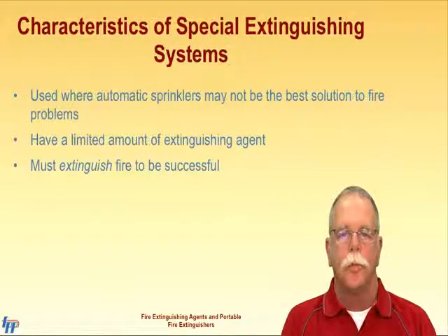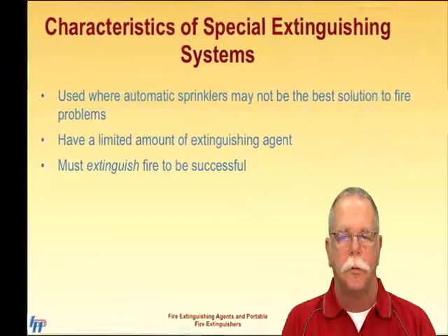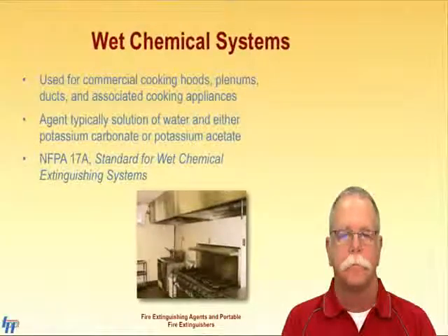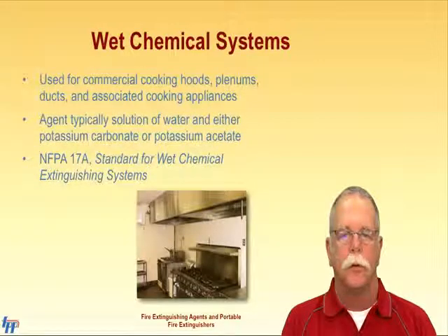Areas such as food preparation areas, combustible metal milling, or highly sensitive electronics are examples where special extinguishing systems may be used. The four types of systems we will discuss are wet chemical, dry chemical, gaseous agents, and foam systems. Wet chemical systems can be messy, and the extinguishing agent may migrate from the fire area to surrounding equipment, possibly even causing damage where there was no fire damage.